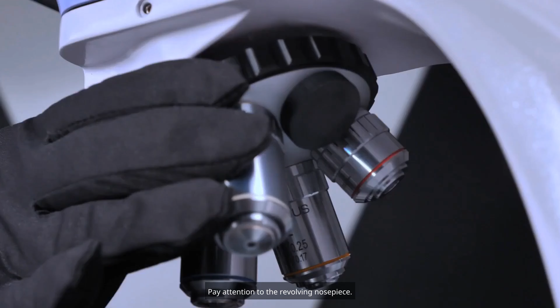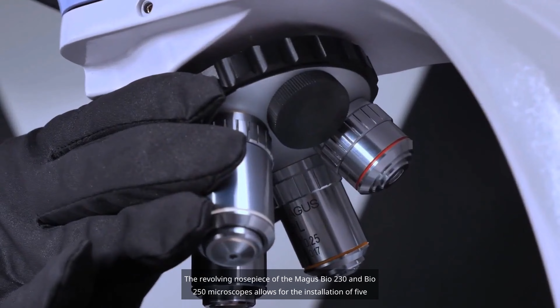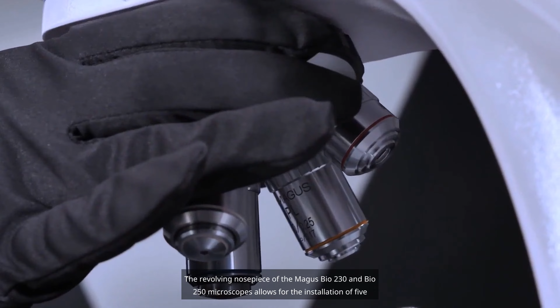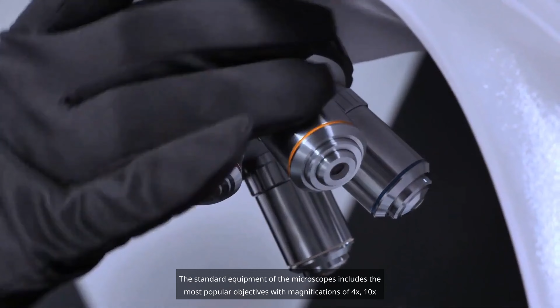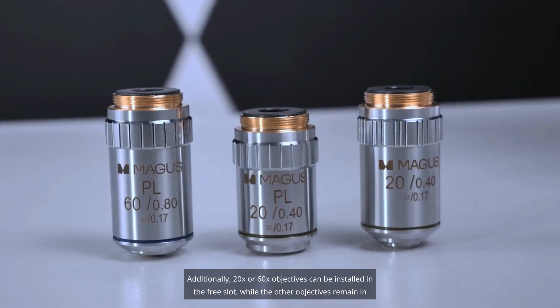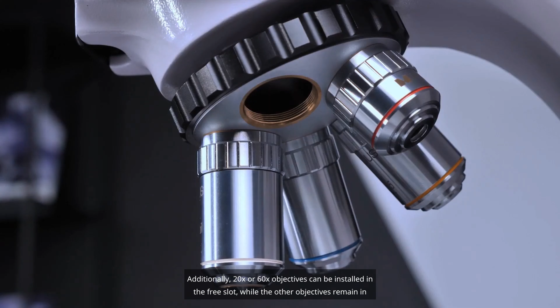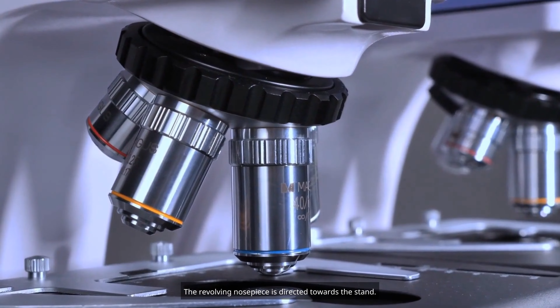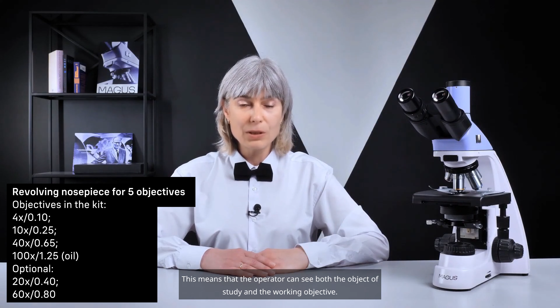Pay attention to the revolving nosepiece. The revolving nosepiece of the MAGUS Bio 230 and Bio 250 microscopes allows for the installation of 5 objectives. The standard equipment of the microscopes includes the most popular objectives with magnifications of 4x, 10x, 40x, and 100x. Additionally, 20x or 60x objectives can be installed in the free slot, while the other objectives remain in the revolving nosepiece. The revolving nosepiece is directed towards the stand. The space above the stage is free. This means that the operator can see both the object of study and the working objective.